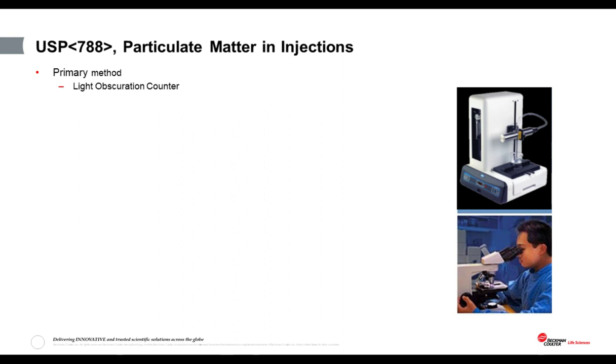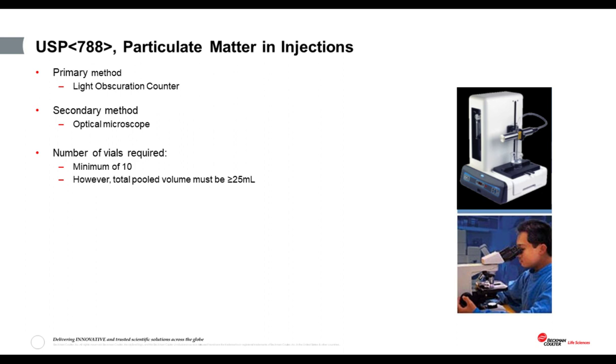So let's take a look at USP 788 first. The primary method specified for carrying out this test in the pharmacopoeia is to use a light obscuration particle counter. And I'll explain the reason why this technology is preferred in a short while. Now, however, should the product under test not be suitable for light obscuration testing, then the USP does allow a secondary method of using an optical microscope and sizing and counting the particles by eye.